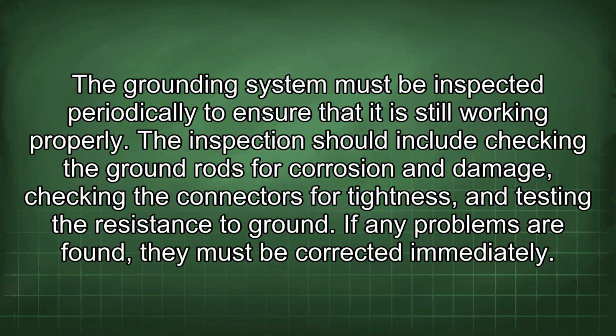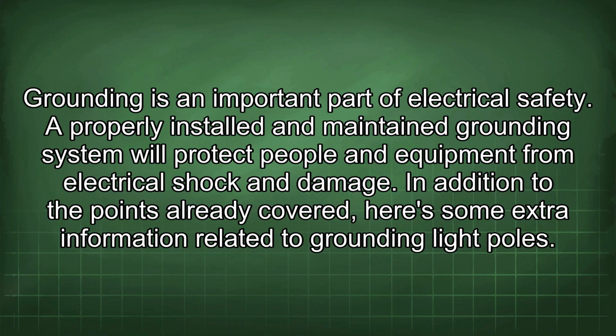The grounding system must be inspected periodically to ensure that it is still working properly. The inspection should include checking the ground rods for corrosion and damage, checking the connectors for tightness, and testing the resistance to ground. If any problems are found, they must be corrected immediately. Grounding is an important part of electrical safety. A properly installed and maintained grounding system will protect people and equipment from electrical shock and damage.